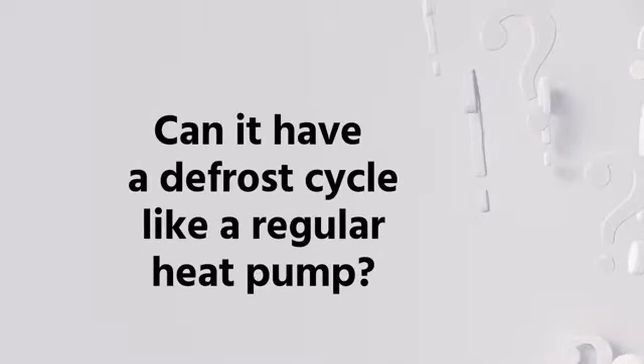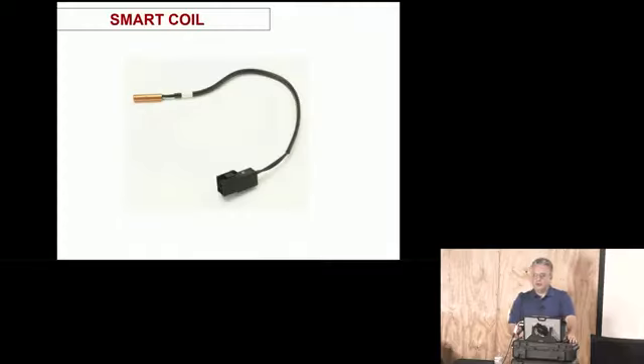And this, yes, sir. No, not like a regular heat pump. It's much more refined. Depending on the manufacturer, you can have a timed defrost. That's every 8 hours. Some manufacturers will just look at the coil and say, we're a little frosty here, let's go to defrost, and it can be anywhere from 2 minutes to 4 minutes.